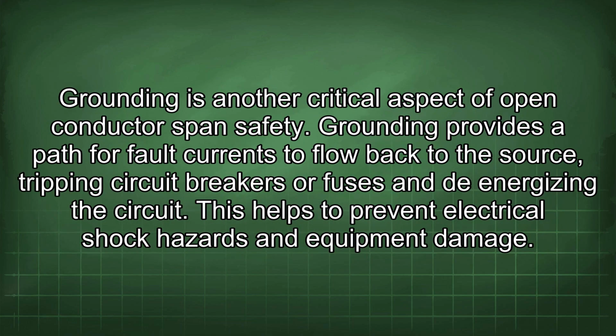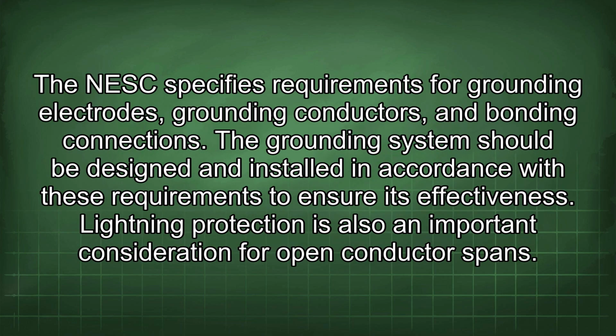Grounding is another critical aspect of open conductor span safety. Grounding provides a path for fault currents to flow back to the source, tripping circuit breakers or fuses and de-energizing the circuit. This helps to prevent electrical shock hazards and equipment damage. The NESC specifies requirements for grounding electrodes, grounding conductors, and bonding connections. The grounding system should be designed and installed in accordance with these requirements to ensure its effectiveness.